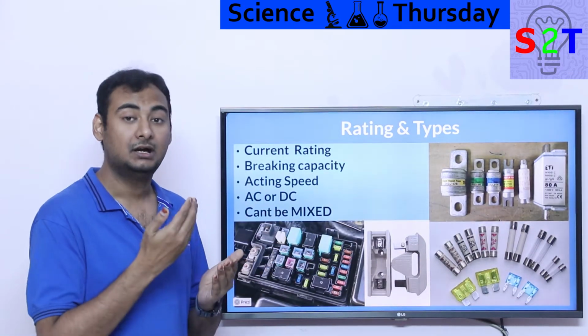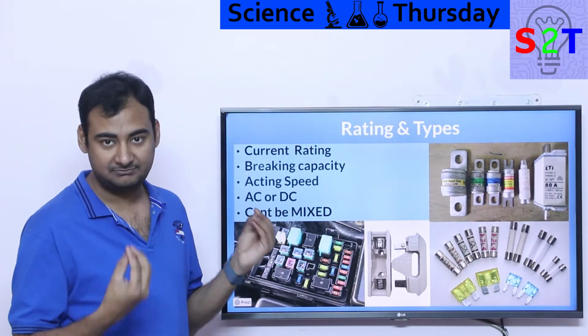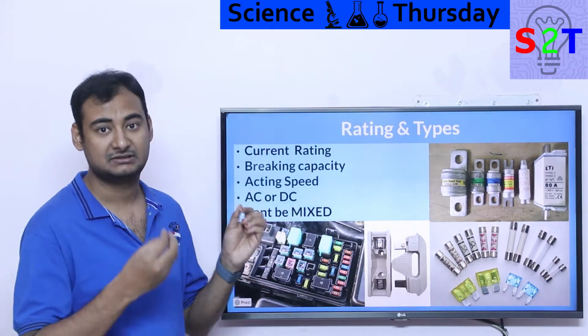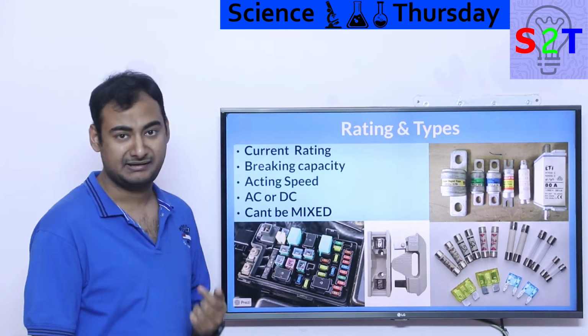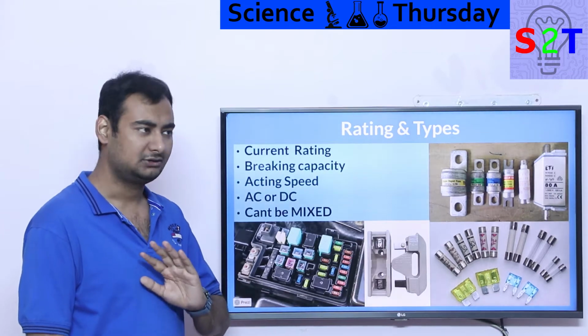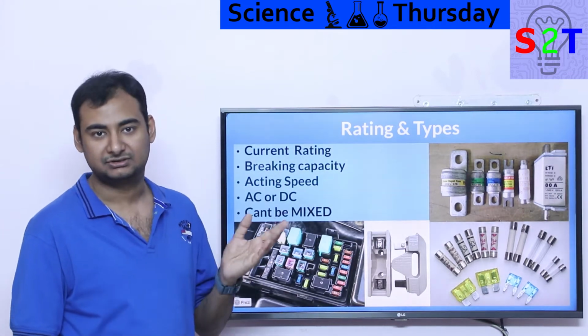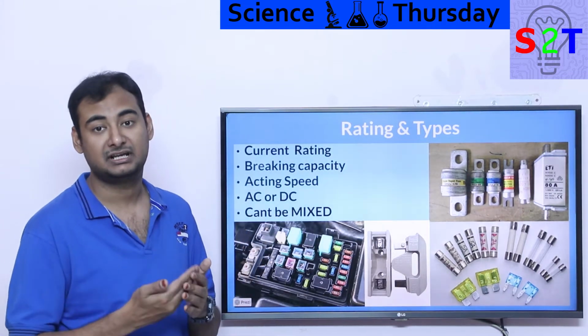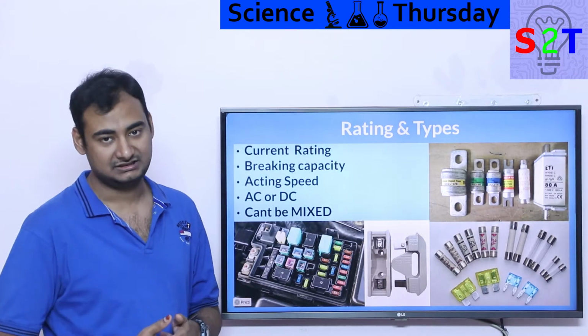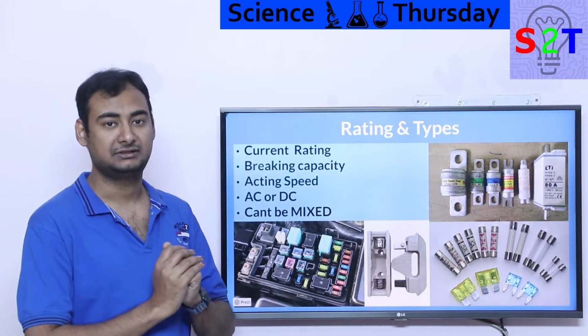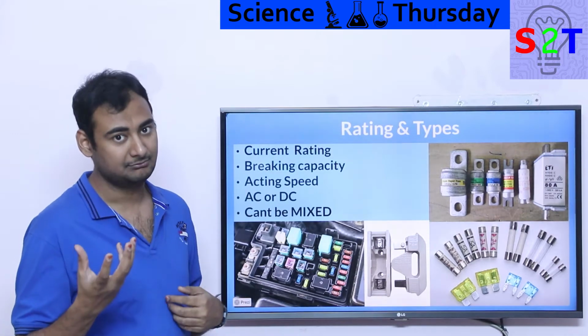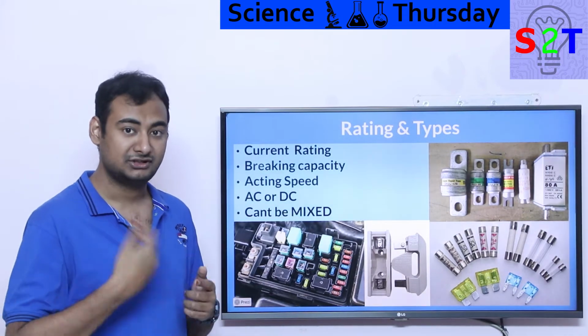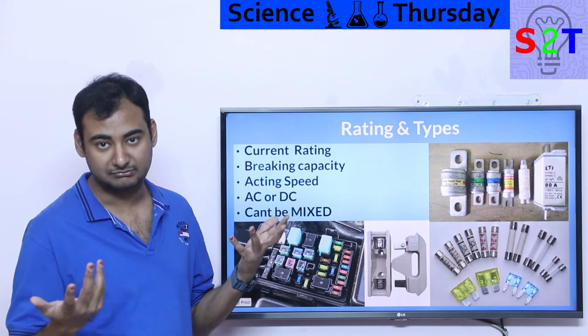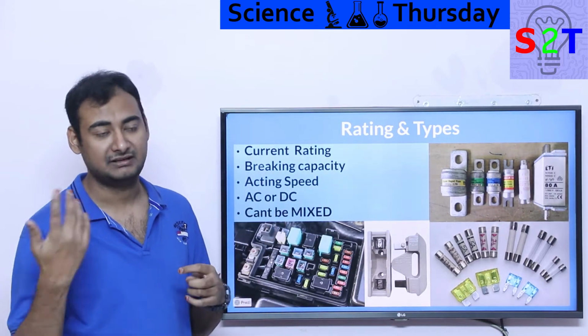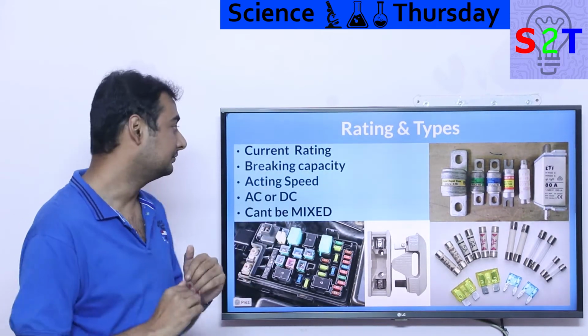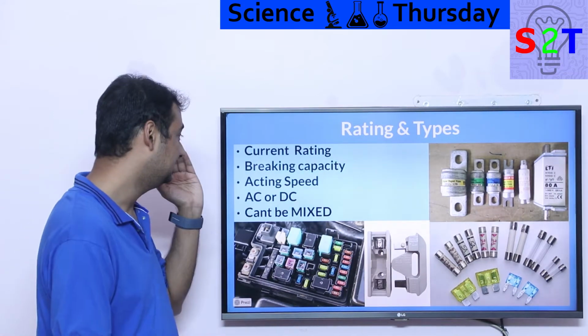For example, say this is a basic lamp system, barely running an LED, only drawing maybe 1 amp maximum. You'd put a fuse that blows at 1.5 amps. So if a short circuit happens, jumping to 10-20 amps instantaneously, the fuse says nope. Or if some bad effect happens and the system starts drawing too much current — overheating, LEDs burning out, drawing 2, 3, 5 amps — the fuse again says nope. That's the first thing you look for: the current rating.